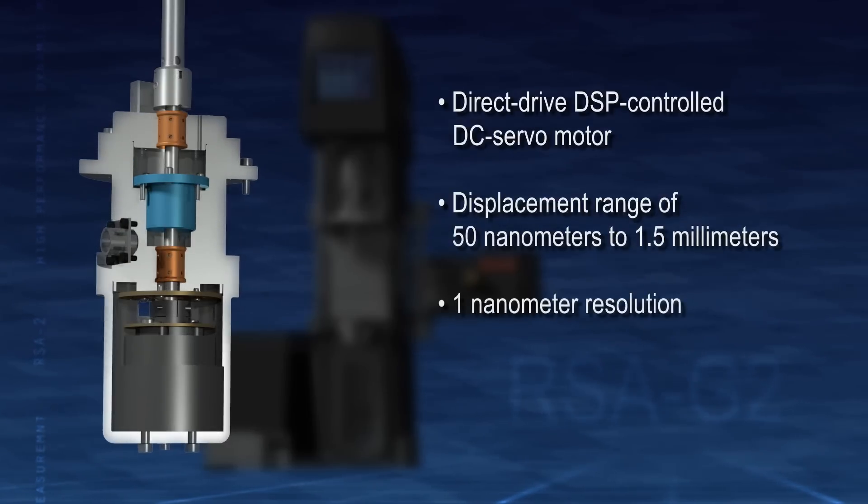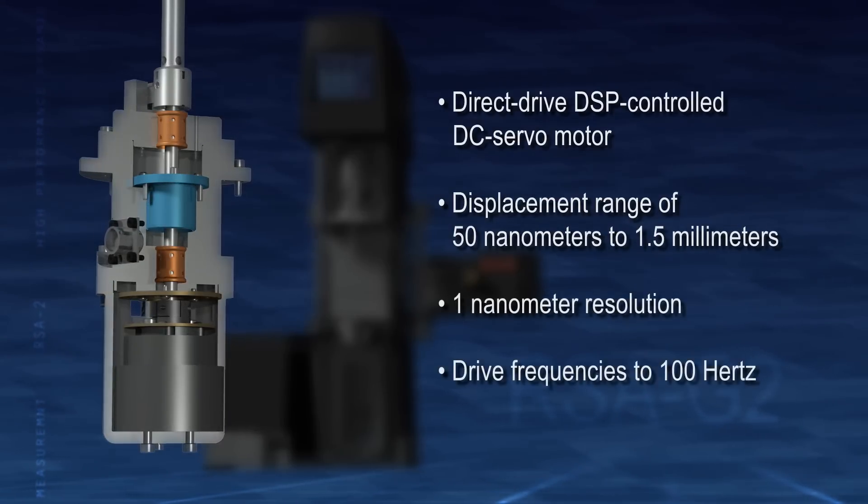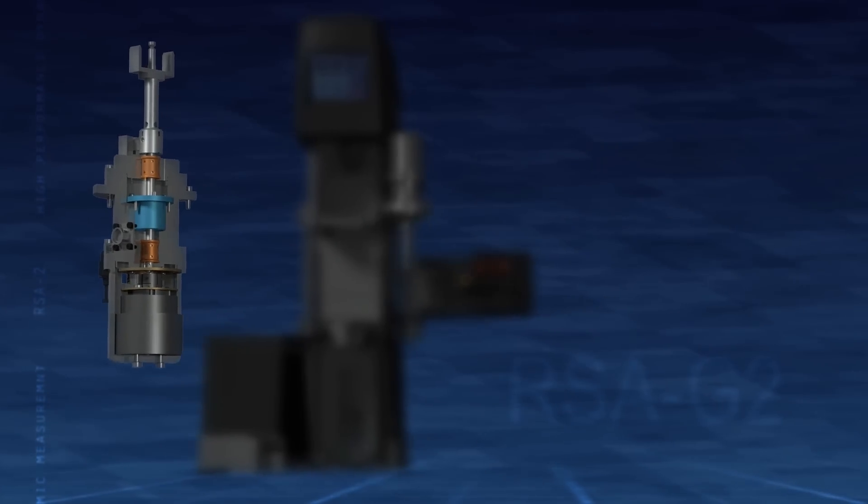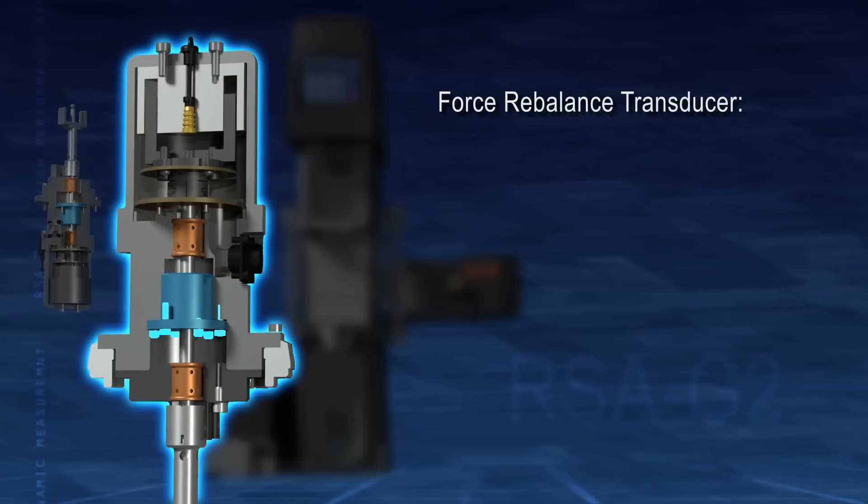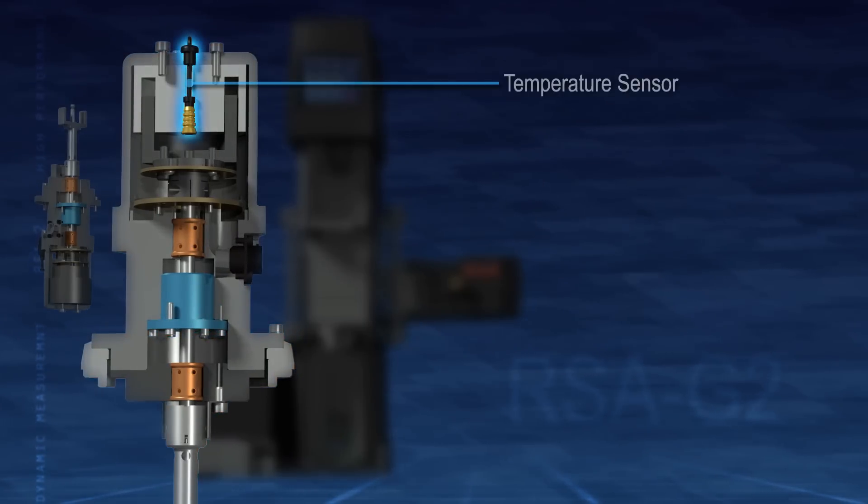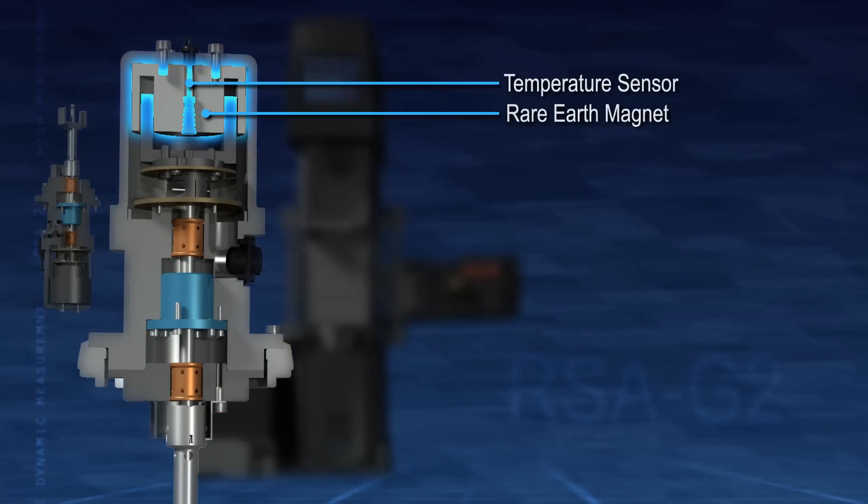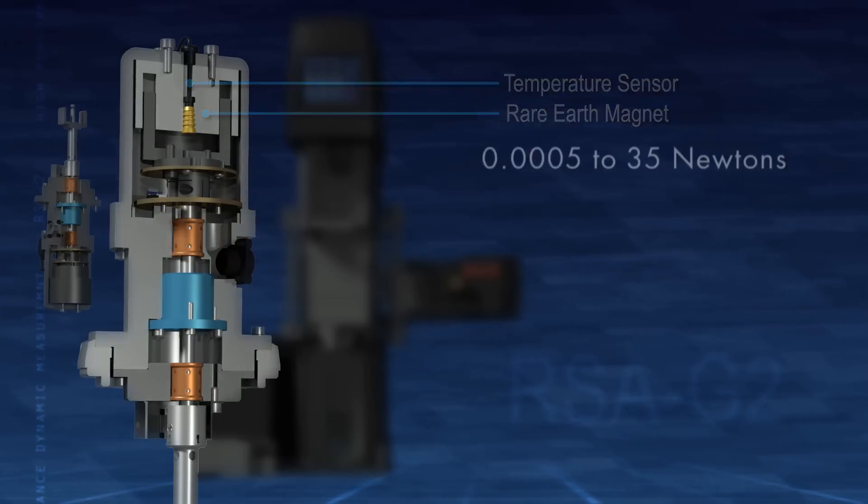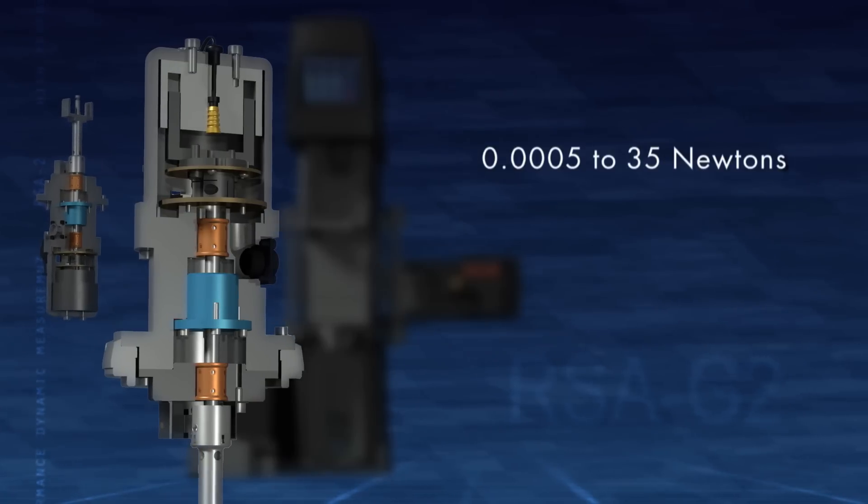One nanometer resolution and drive frequencies to 100 hertz. Sample stress is measured independently by a force rebalance transducer, or FRT, with rare earth temperature compensated magnets ensuring the most accurate force measurement over a wide range of 0.0005 to 35 newton.